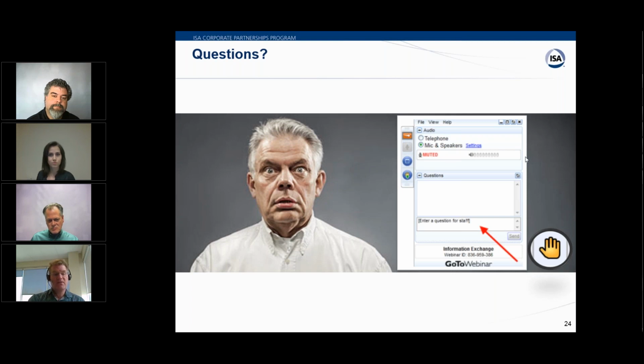Now, the saving grace if you're out is that, remember, for control, it's not always the accuracy that's most important, but the repeatability. So as long as you're consistently wrong, so instead of being 7, it's consistently 7.2, you can put that offset into your control system and still control at 7. But if you're using an acid and a base, it's just the rules of calibration. And Ned and Roy can verify that it's got to be a minimum of 3. Some people say 4 times the repeatability of the measurement system.